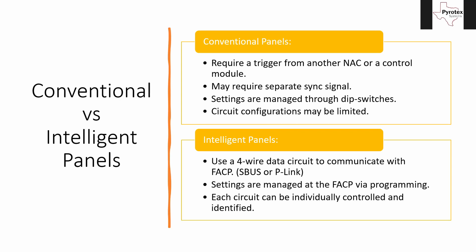The power supplies may require a separate sync signal. That's going to depend a lot on what you're putting in the building and how many different panels there are. If all the strobes are powered off of the same power supply, you will not need a separate sync signal. If you have multiple power supplies, or some strobes are powered off your control panel and others off your power supply, you will need a signal that syncs the panels together.